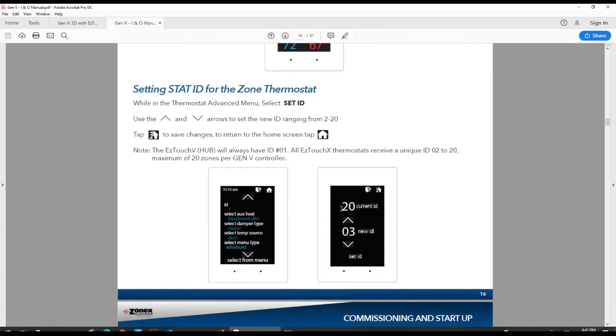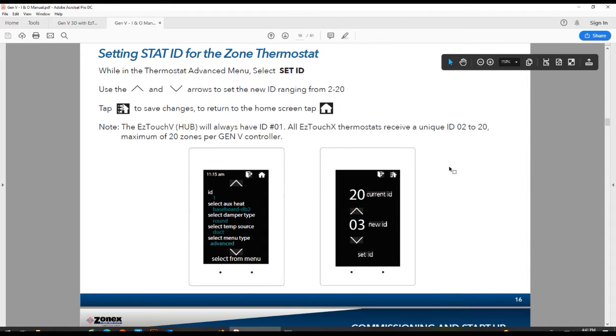So in this system, we need to configure our thermostats, each with its own unique ID. If we had a Gen V control system with, say, 10 zones, we're going to ID them 1 through 10. Do note that your hub thermostat is hard ID'd as number 1, so you will not need to ID it. You'll need to ID the remaining 9 thermostats with an ID ranging from 2 through 10.